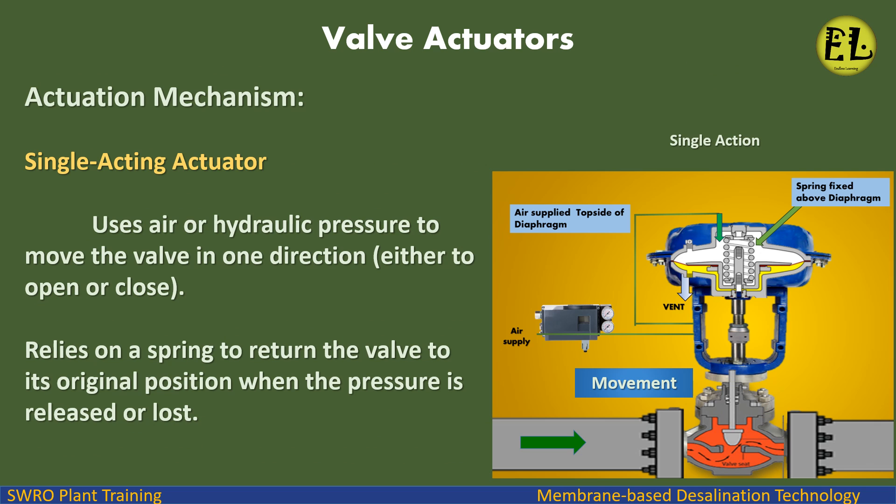Types of valve actuators — actuation mechanism. Single acting actuator: uses air or hydraulic pressure to move the valve in one direction, either to open or close. It relies on a spring to return the valve to its original position when the pressure is released or lost.